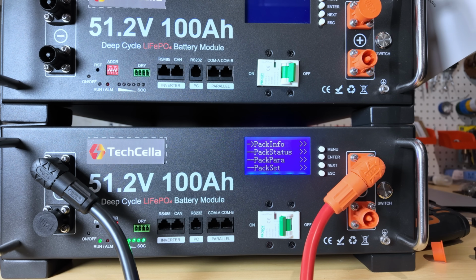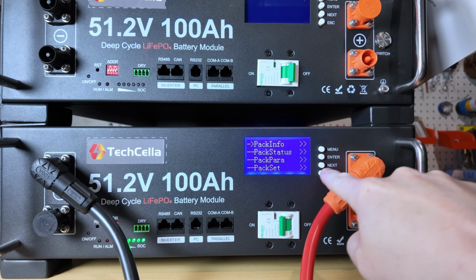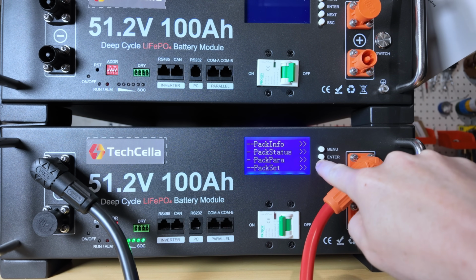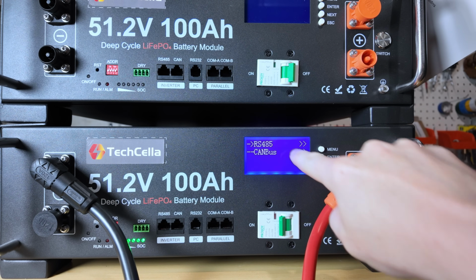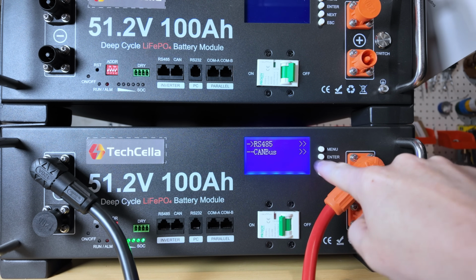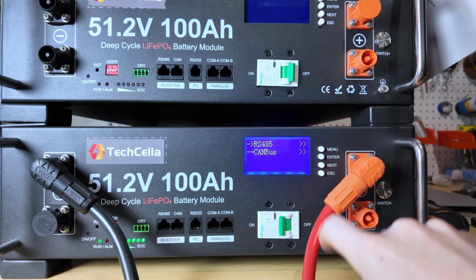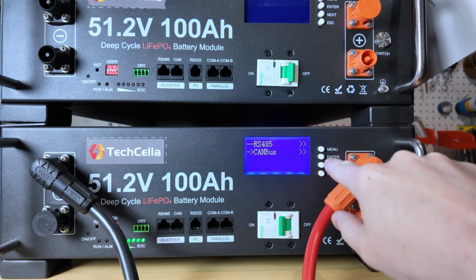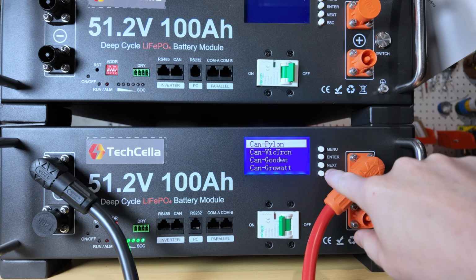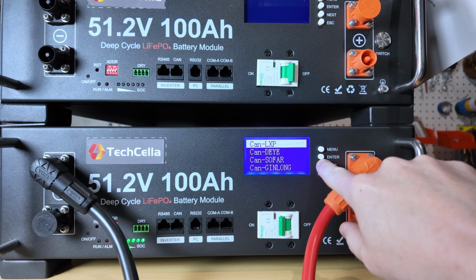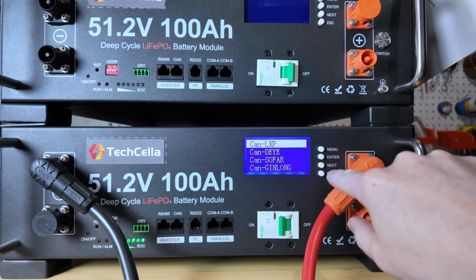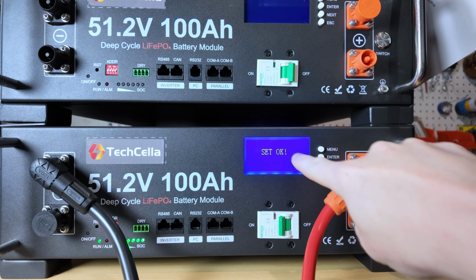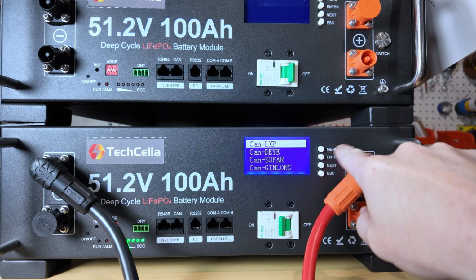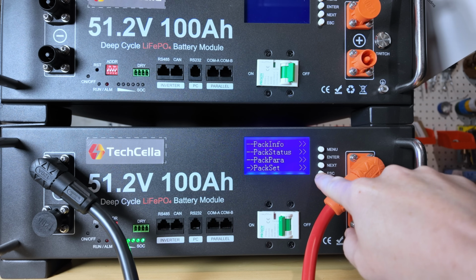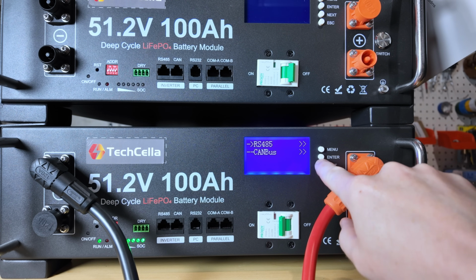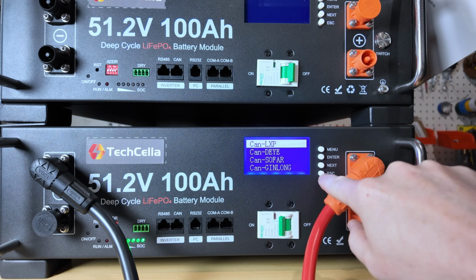So to change the battery protocol, we're going to come down to pack set. You see the little arrow right here, so we'll hit next and then enter. We can do RS-485 or CAN bus. I'm just going to do CAN bus, but it's going to be the same thing for both. We'll go to next and hit enter. And so we're going to scroll down until Lux Power, LXP, and hit enter. Set OK. And then we'll escape out. We'll come back in and just make sure it's still on Lux Power.